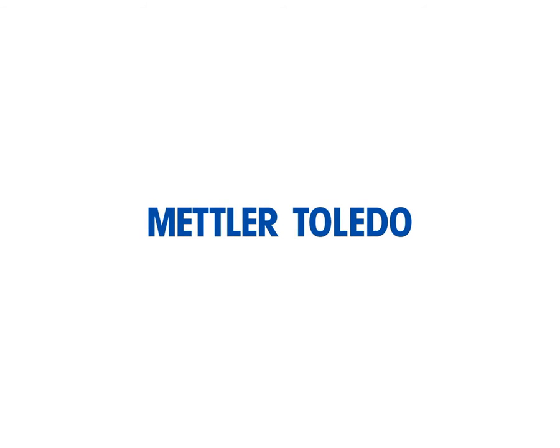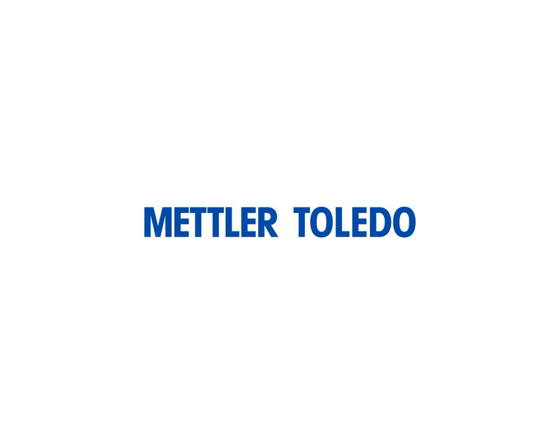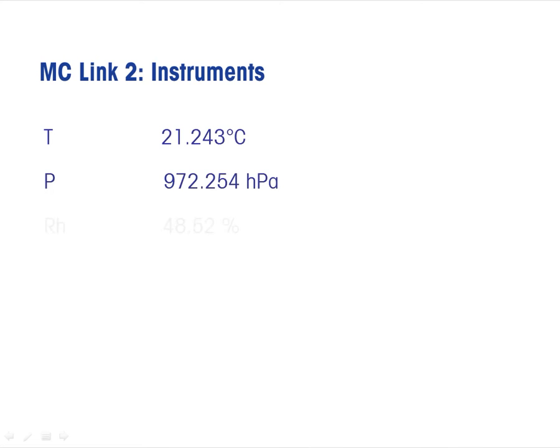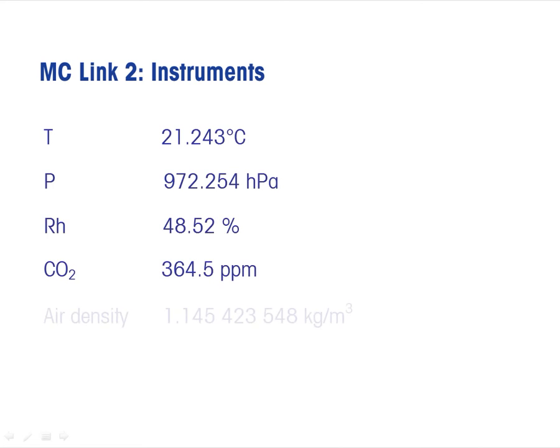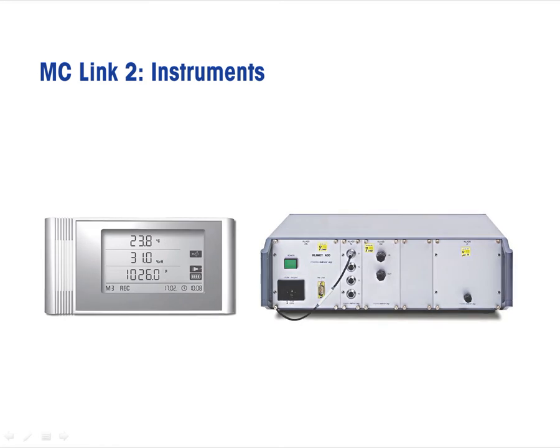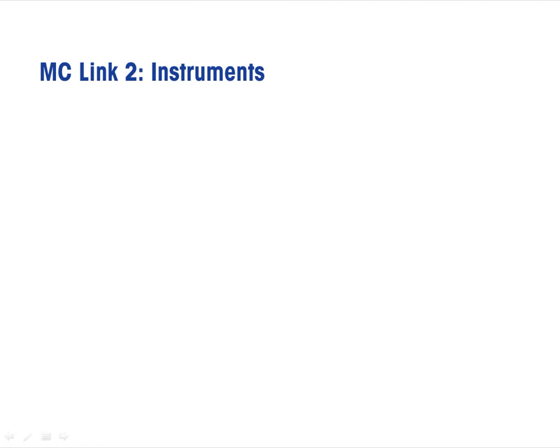To increase the accuracy of mass calibration and correction of air buoyancy influences, climatic parameters are required. These parameters are retrieved from a climatic sensor of sufficient accuracy to fulfill the combined accuracy requirements.